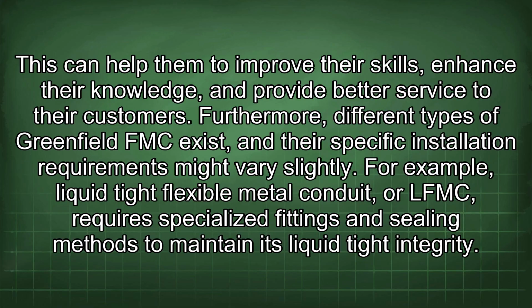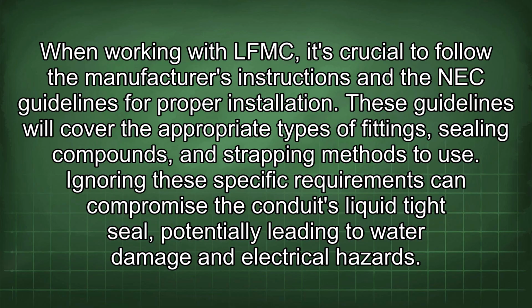customers. Furthermore, different types of Greenfield FMC exist, and their specific installation requirements might vary slightly. For example, liquid-tight flexible metal conduit, or LFMC, requires specialized fittings and sealing methods to maintain its liquid-tight integrity. When working with LFMC, it's crucial to follow the manufacturer's instructions and the NEC guidelines for proper installation. These guidelines will cover the appropriate types of fittings, sealing compounds, and strapping methods to use. Ignoring these specific requirements can compromise the conduit's liquid-tight seal, potentially leading to water damage and electrical hazards.